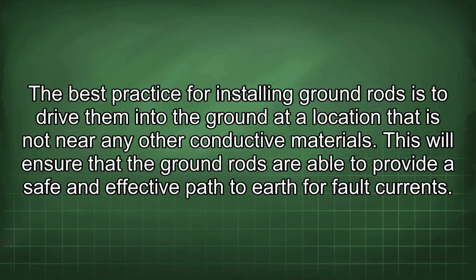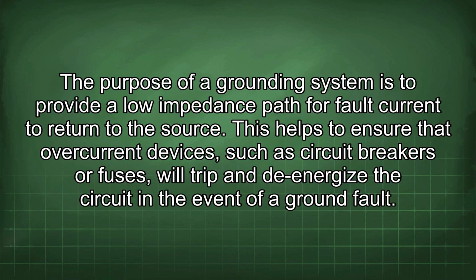The best practice for installing ground rods is to drive them into the ground at a location that is not near any other conductive materials. This will ensure that the ground rods are able to provide a safe and effective path to earth for fault currents. The purpose of a grounding system is to provide a low impedance path for fault current to return to the source. This helps to ensure that overcurrent devices, such as circuit breakers or fuses, will trip and de-energize the circuit in the event of a ground fault.